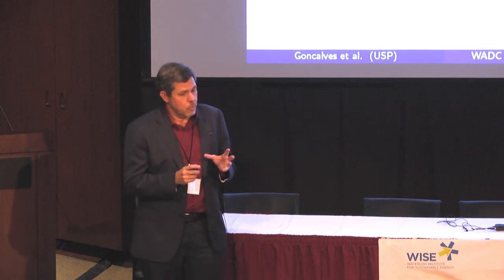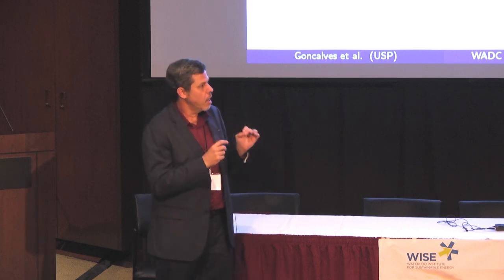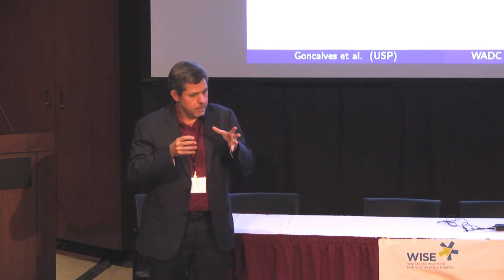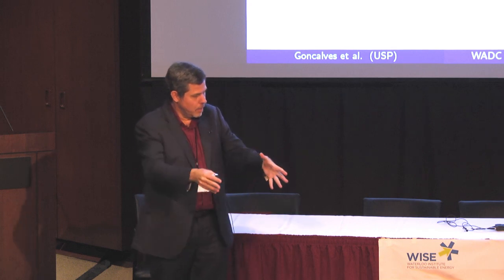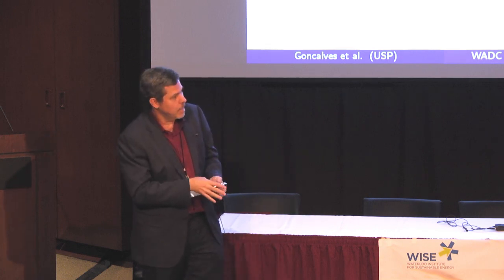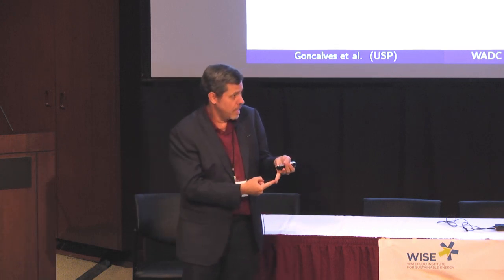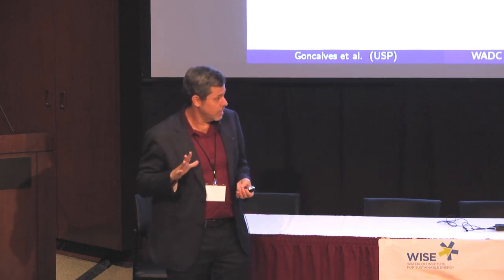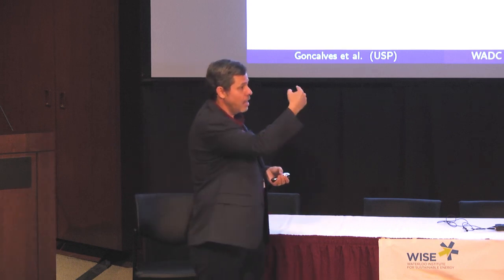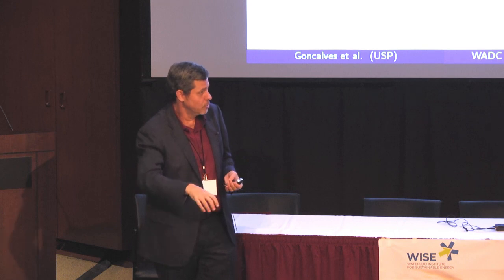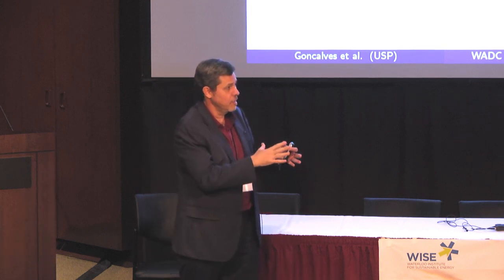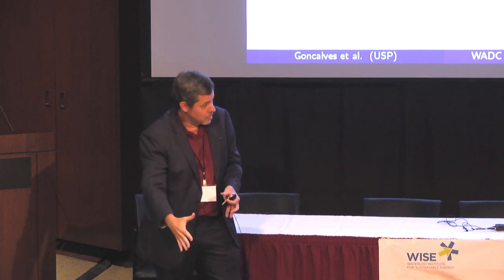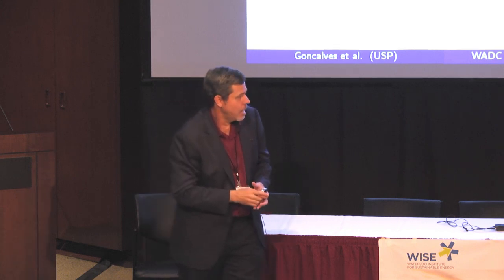But one thing we kept in mind is that we cannot rely on the centralized controller to be the main contributor to damping, because it is subject to cyber attacks, to structure failures, to several other things. So you might have to disconnect it. And when you disconnect it, you have to rely on the PSSs to render the system stable. So we only considered the situations in which the system, when the controller was taken out, was still stable because of the actions of the PSS. I don't know if that answers your question.